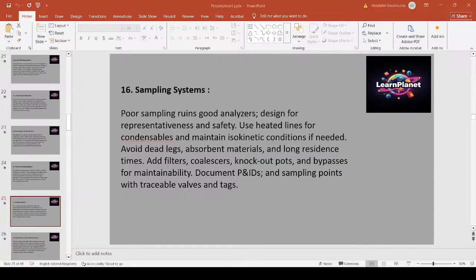Example: for wet gas samples to a GC, use a heated sample probe, heated transfer lines, and coalescers to remove liquids before the GC.